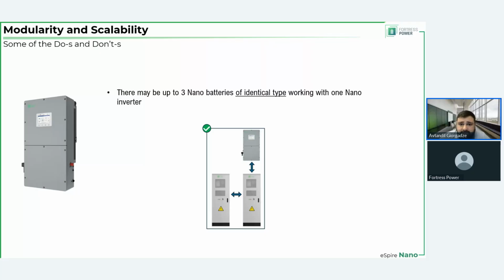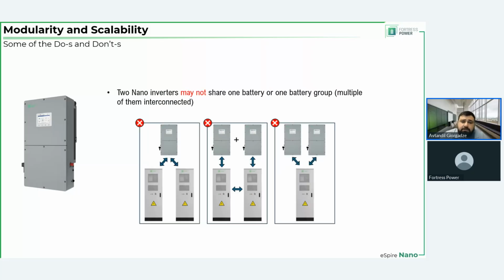So for example, if you have one 60 kilowatt inverter and the other 60 kilowatt inverter, one inverter may have, I don't know, 240 kilowatt hour batteries, and the other may have 160 kilowatt hour battery, because these batteries are not connecting in parallel, which means that the voltage difference that they have is not going to produce any problems, because the inverter will manage the power flow to each of them, but you are not paralleling them. So one will not backfeed into the other because it has higher nominal voltage than the other. And 2 Nano inverters never, ever are allowed to share 1 battery or multiple batteries connected in parallel. Very straightforward.